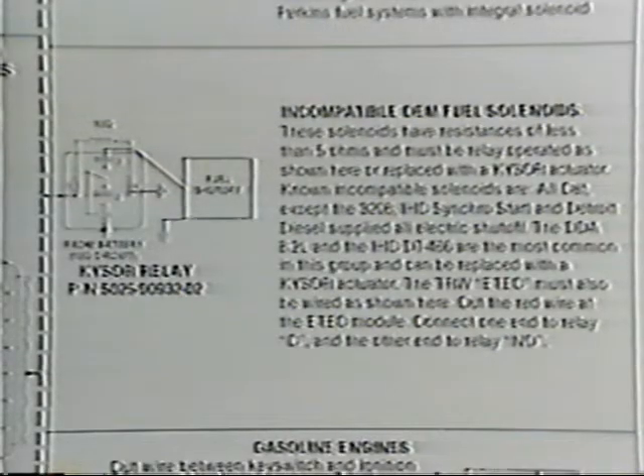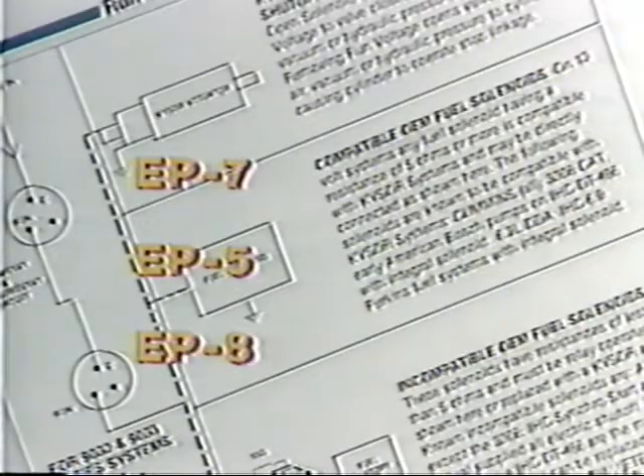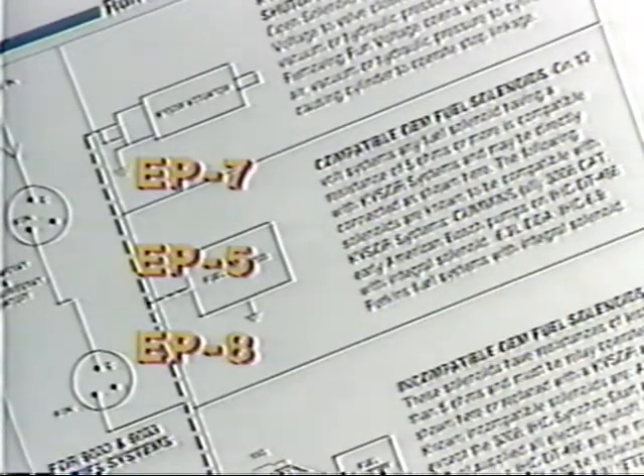Troubleshooting area 4. In the very beginning of this section, we talked about 3 types of fuel shutoffs. 2 could be directly connected to the shutdown system, and 1 could not. That one has a current requirement that the KYSOR system cannot handle and must be installed using a relay. Always consult this page in publications EP7, EP5, or EP8. It will tell you how to determine if you need a relay and how to wire it if you do. If you do not use the relay when required, the problems will range from difficult starting to no start to destruction of the entire alarm and shutdown system.